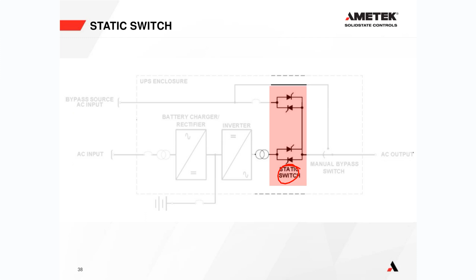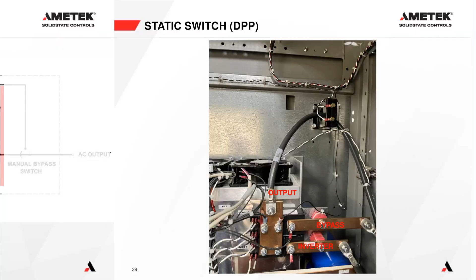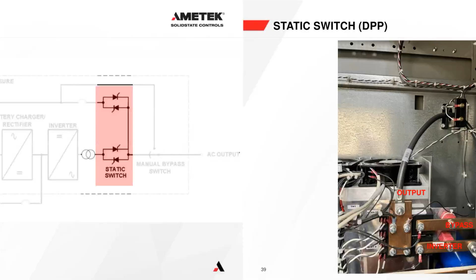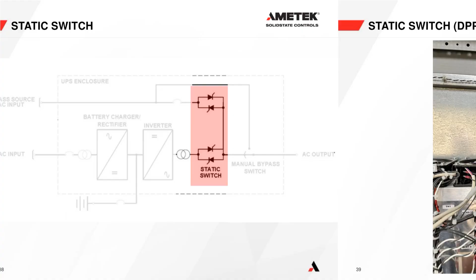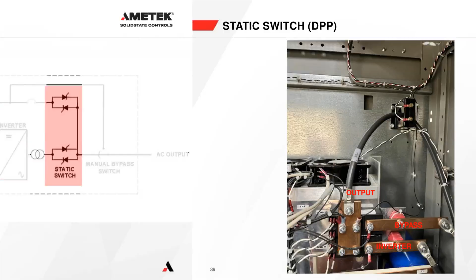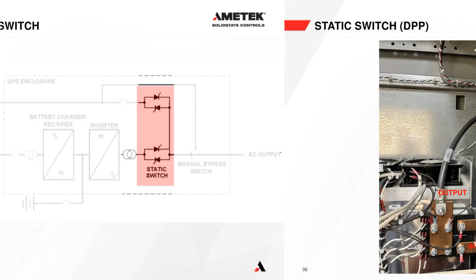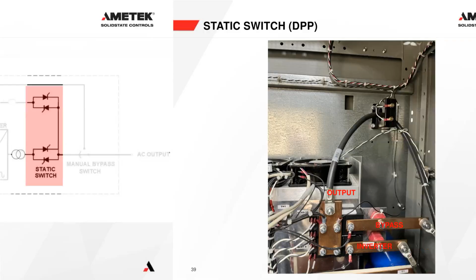So here on the single phase system, we only switch the hot, we don't switch the neutral. You can see here we have our inverter terminal going to this bus bar, then we have our bypass going onto this bus bar. Once again, we have an SCR pack behind here, and an SCR pack behind here. If we go back to the previous slide, this is our inverter SCR pack, which is this pack here, and this is our bypass SCR pack, which is this pack here. As I said, both switches on the output are connected together, so this bus bar here is the output of the static switch, and that goes out through a CT out to the load circuits connected to the UPS.